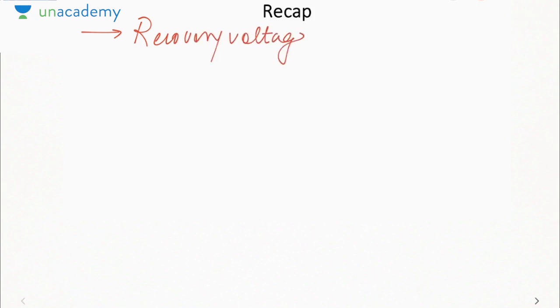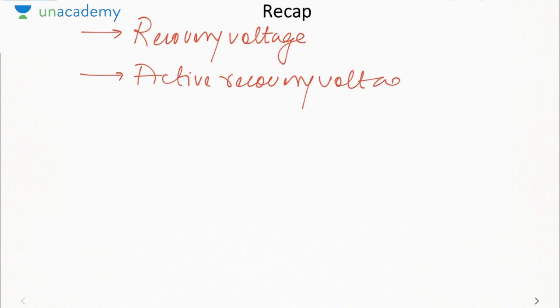Recovery voltage was the RMS value of the power frequency voltage that appears across the circuit breaker contacts when the arc is extinct. Then we saw active recovery voltage, which was the instantaneous value of recovery voltage which appears across the circuit breaker contacts when the arc is interrupted.